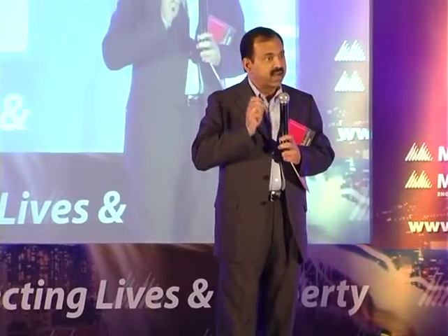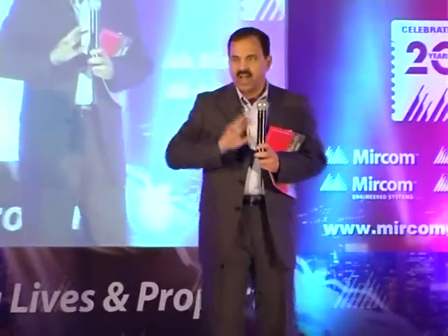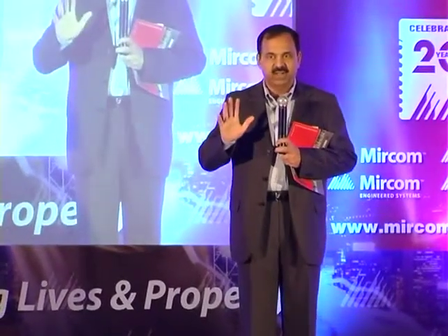Programming for cause and effect in having 350 devices on the loop. There are instances where we need to increase the number of loops. There are even instances where we have to increase the number of panels to achieve the cause and effect programming. And I do not talk here in terms of theory.